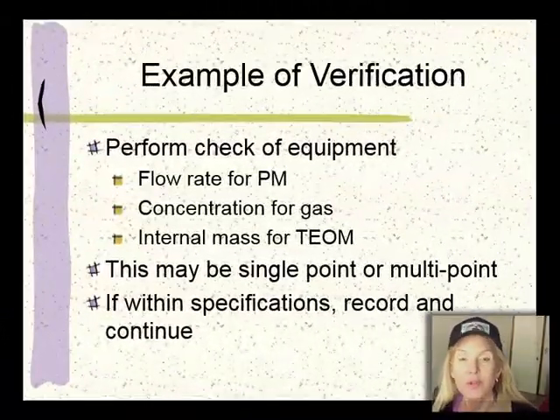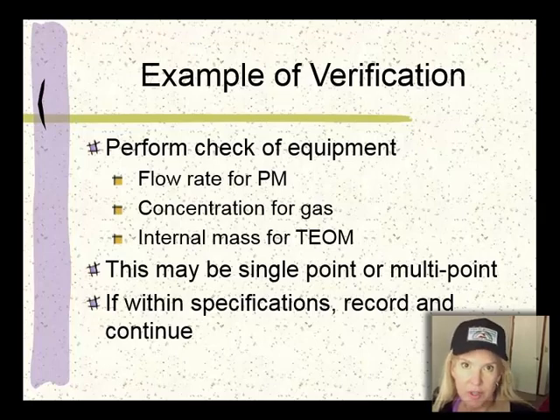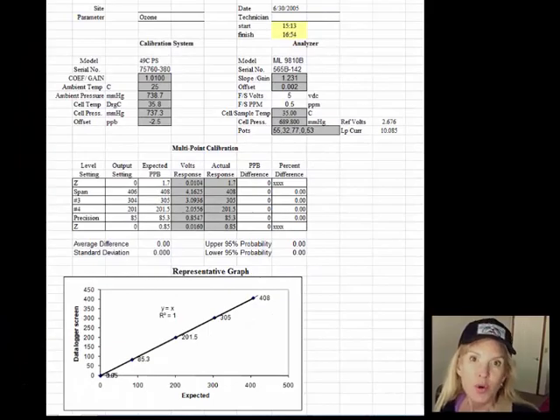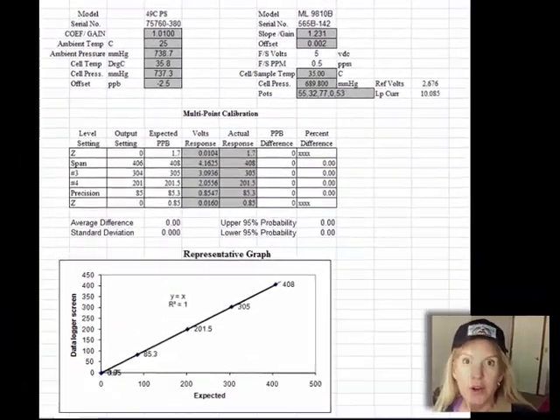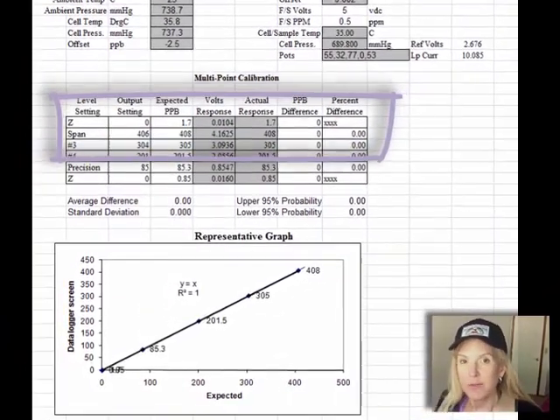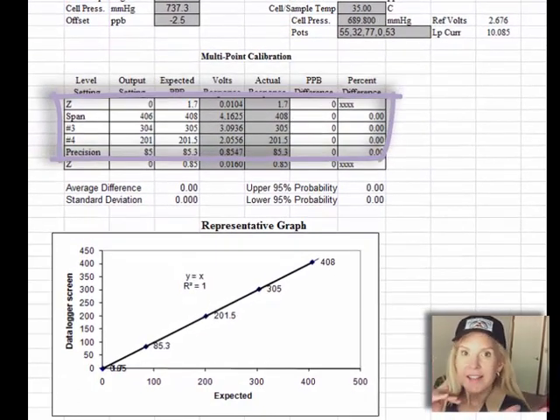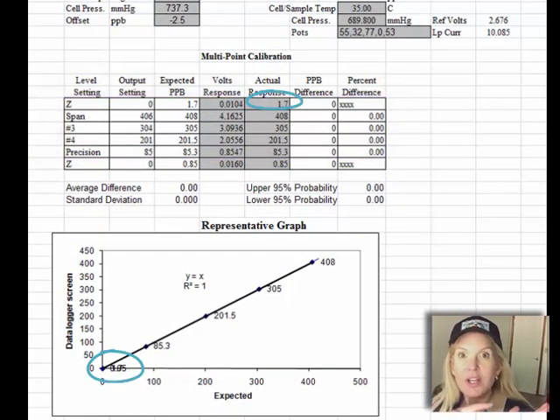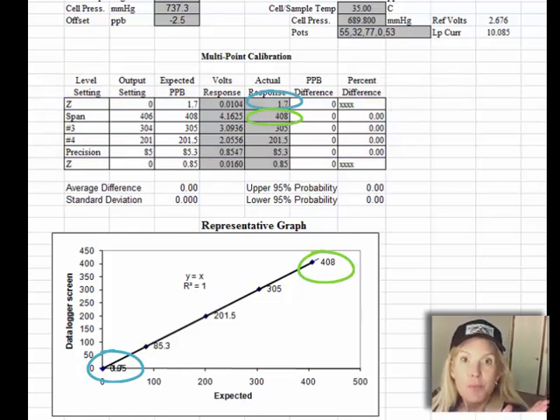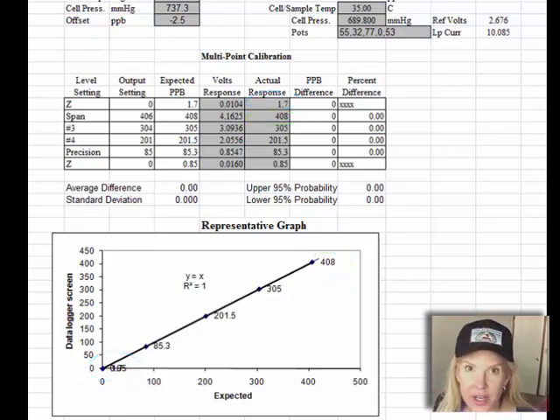Remember, verification is when you verify that your instrument is operating within limits. And when we talk about, say, doing a 2-point or a 5-point verification, that means you take 5 different points on the line that goes from 0 to higher concentrations. Or if you're talking about flow rate, measuring how well your field instrument compares against flow rate or some other parameter like temperature or pressure measured by a handheld transfer standard.